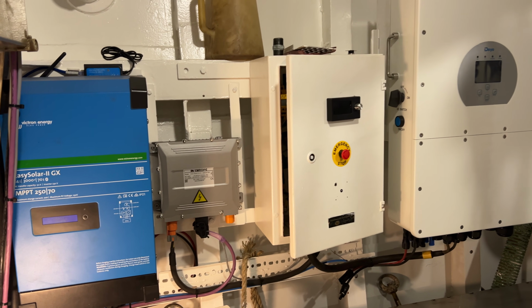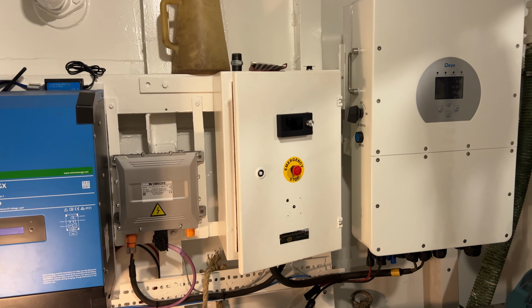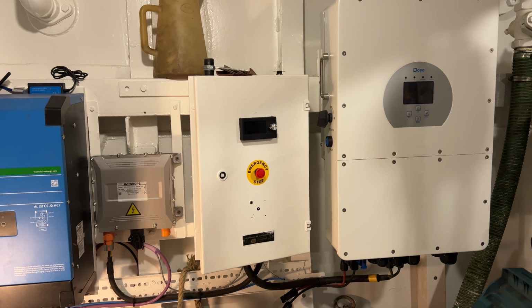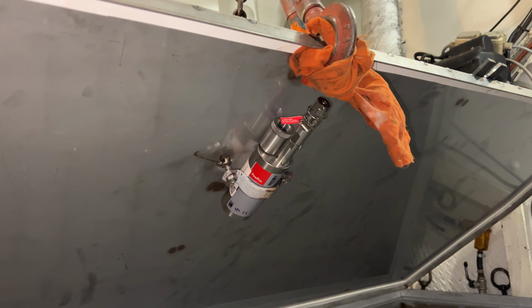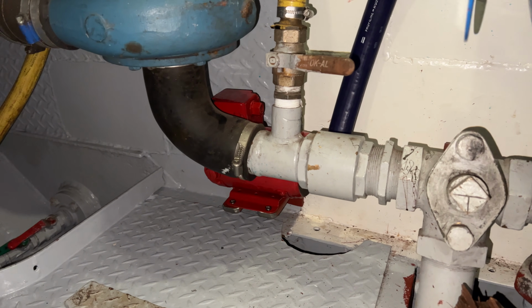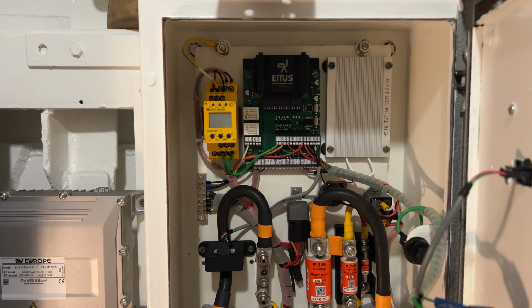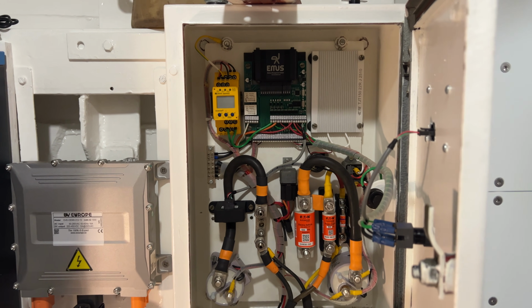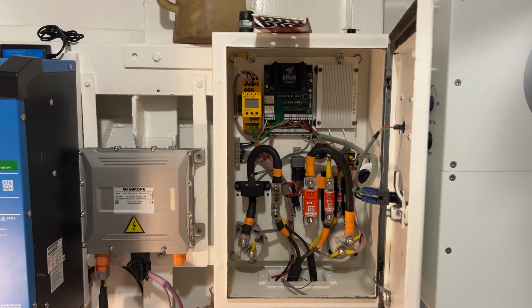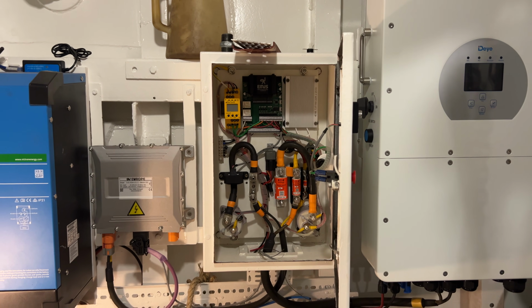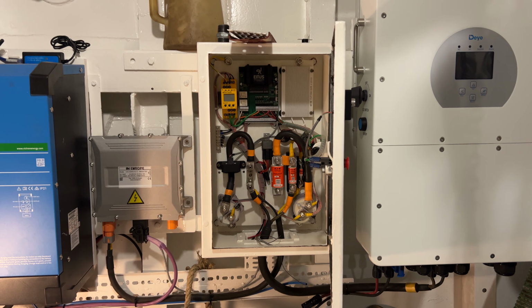We might be sleeping or not even on the boat when something goes wrong. The BMS is the first automatic protection, the aerosol is the second and the flooding system is the third. We could have the BMS control the total flooding pump as well, with all the temperature sensors that it has inside the batteries. But we still want it to work even if all our sensors are cooked, so we kept it simple. And if we come back to the ship in the morning and we see that all our batteries are flooded, we will probably say a couple of bad words, but the ship is saved and so are we.